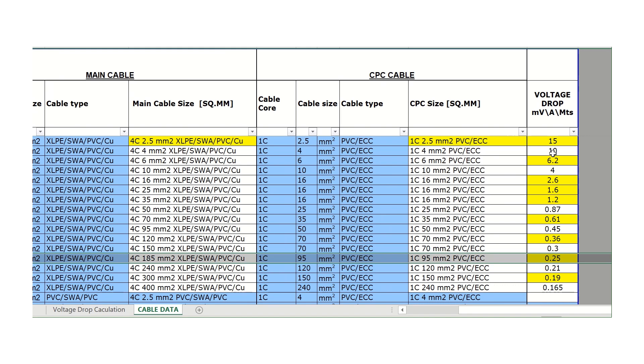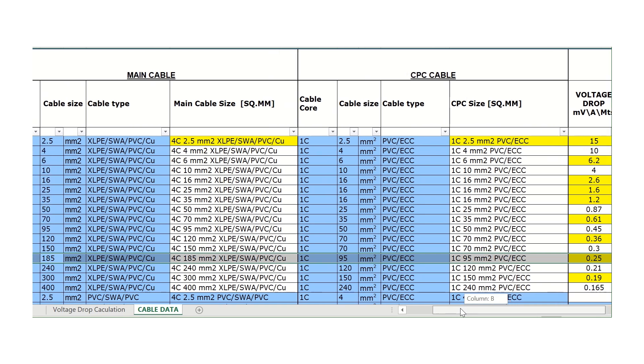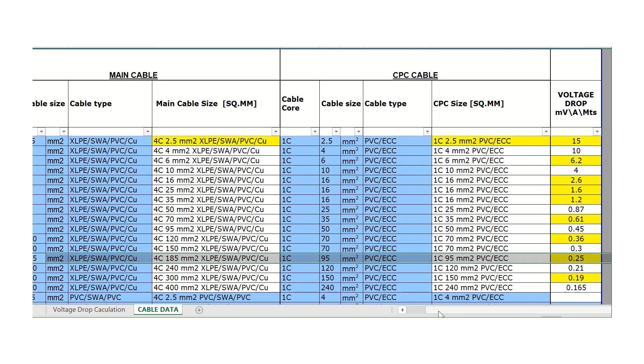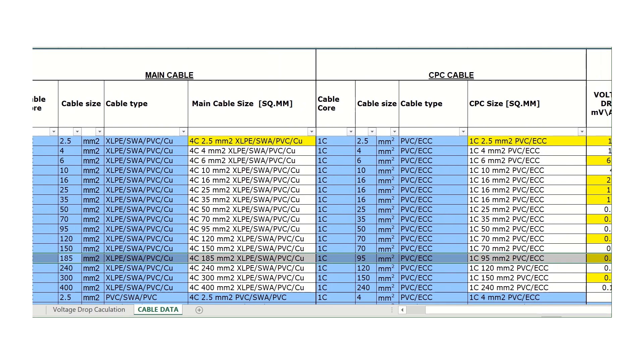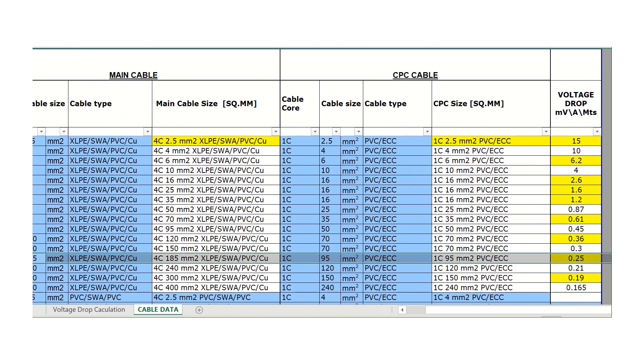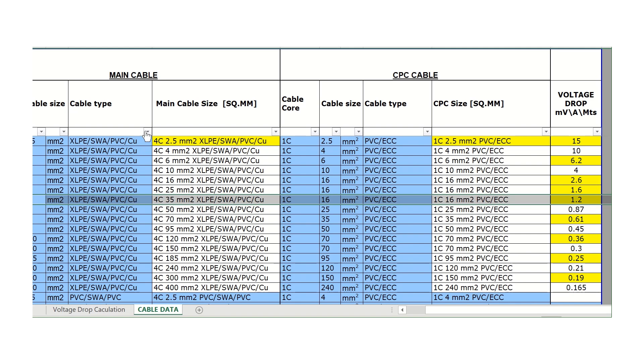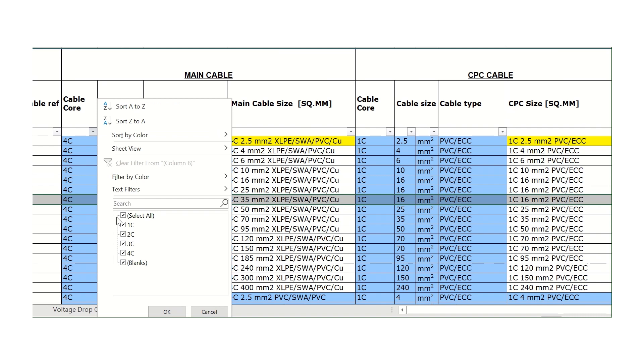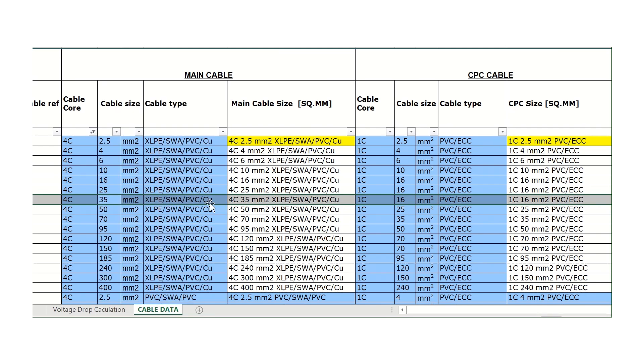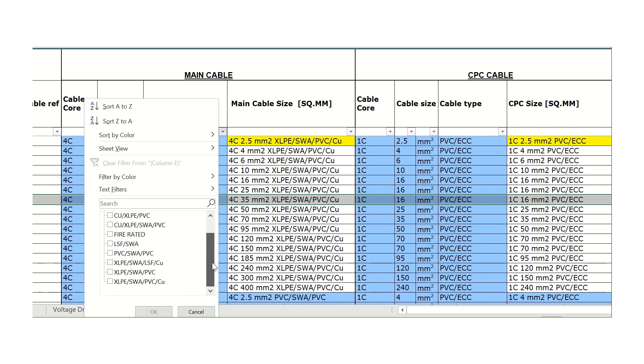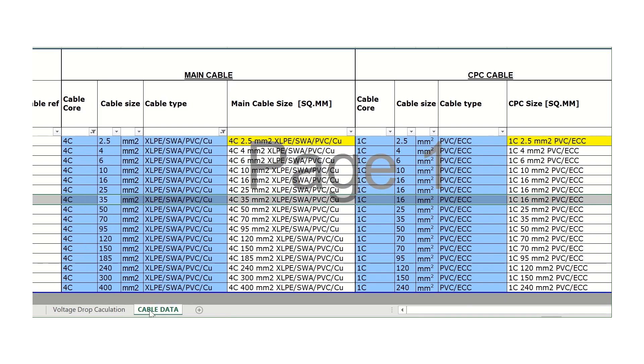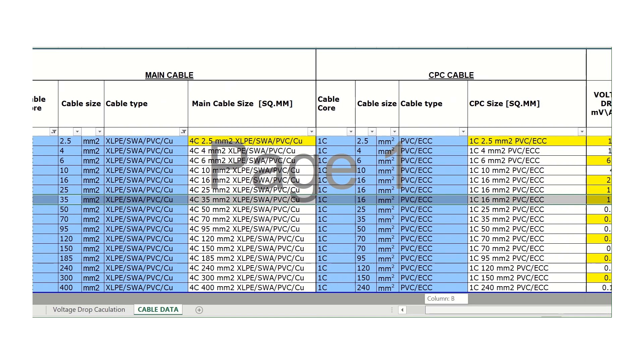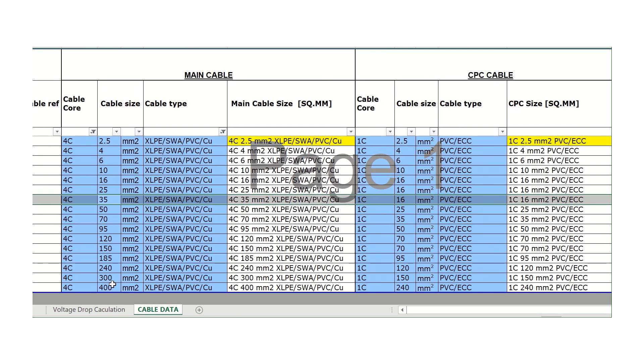These are the MV values for each cable size. For example, for a 185mm² cable, the voltage drop MV value is 0.25. For a 50mm² cable, the MV value is 0.87. For demonstration purposes, I selected four core cable type XLPE SWA PVC copper cable, and I get all values from 2.5mm up to 400mm cable sizes.